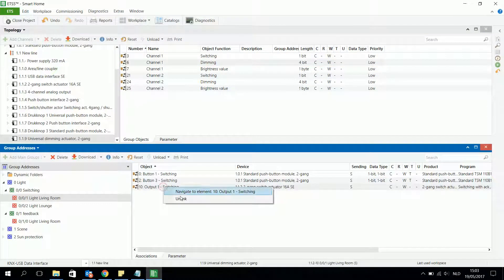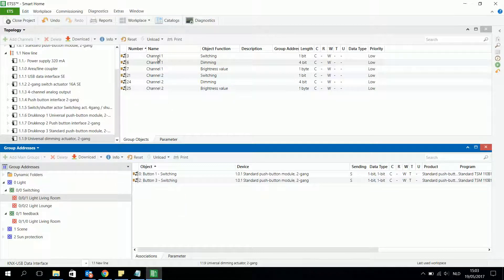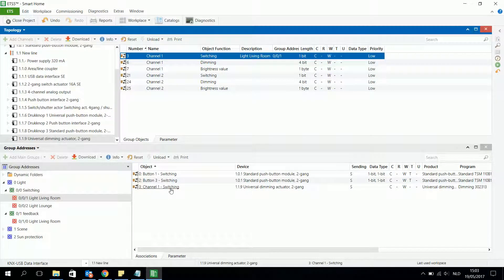I start by unlinking this output. For the light in the living room I want to dim it, so I take channel 1 switching object and associate it with pushbuttons 1 and 3. This way I can switch the light on or off with channel 1 via pushbuttons 1 and 3 on the universal dimming actuator.